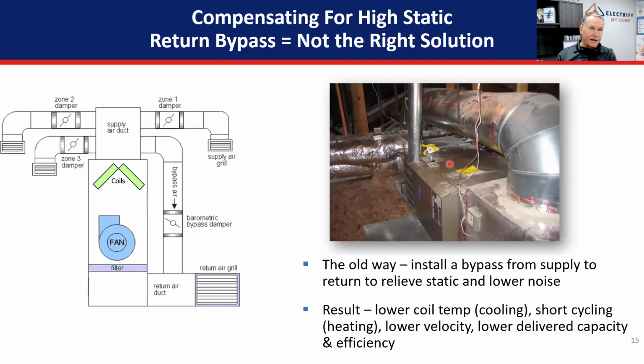They're a normally closed device. If they ever went bad, they just wouldn't open. So it had to open somehow and not close back up. And it did that because the spring lost so much pressure from opening and closing so many times. But our customers never felt that, because there was so much hot air coming out of here that by the time the fan in the furnace cooled down that limit switch, they still had nice warm air coming into the house. They literally did not know it's cycling on the limit switch. Those limit switches are supposed to open and close like 20,000 times before they go bad. So if the limit switch goes out, we have to figure out why. And if you see one of these, you know why, right?